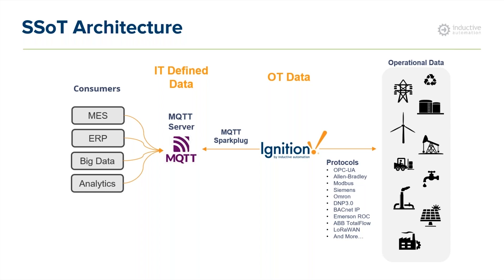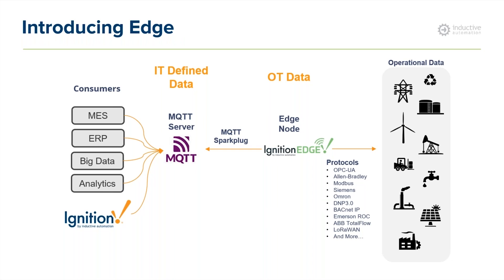When you have remote assets or critical machines on the plant floor where you need local HMIs or distributed systems, that's where Ignition Edge becomes an important part of the architecture. You can leverage Ignition Edge near those PLCs and edge devices, connect to that data, pull it at faster rates, and publish that data securely and by exception to the MQTT server. From there it's made available to a centralized Ignition SCADA system or any other application. By doing this, we're taking the brownfield world and bringing it into a modern infrastructure.